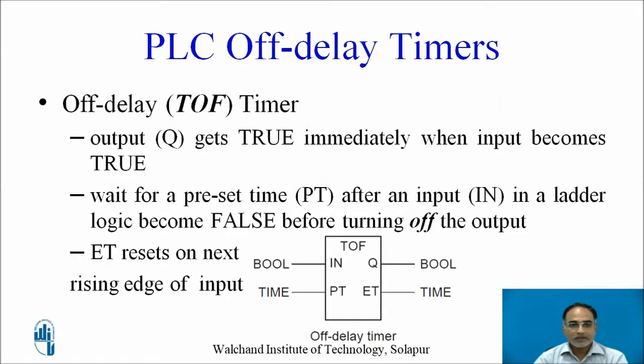Let us understand more about these off delay timers. In off delay timers, output Q gets true immediately when input becomes true, but it will wait for a preset time PT after the input in a ladder logic becomes false before turning off the output. The ET value resets on every next rising edge of input.